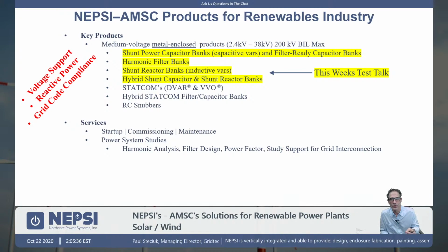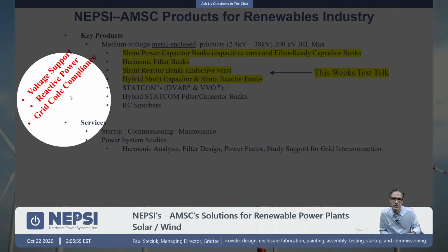Remember, NEPSI is a metal-enclosed equipment supplier, which means that all of our systems come fully integrated with all switching, all protection, and all control. These are products that supply reactive power or consume reactive power. It's for voltage support oftentimes, and it's oftentimes there for grid code compliance.